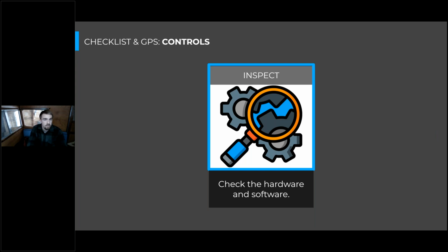But while you look at this hardware, you want to be careful, because there is electricity flowing in and out of it. So you need to make sure that there's someone qualified to do the maintenance and inspection of this. And then the other half of this inspection is inspecting the software. That is whoever is in charge of monitoring the equipment, usually building maintenance or a management firm. They just check in to make sure that they're not receiving any really strange values that don't align with how the system was previously operating.